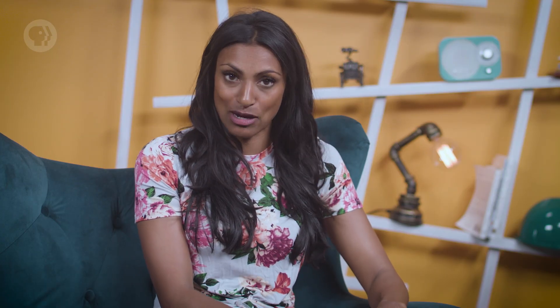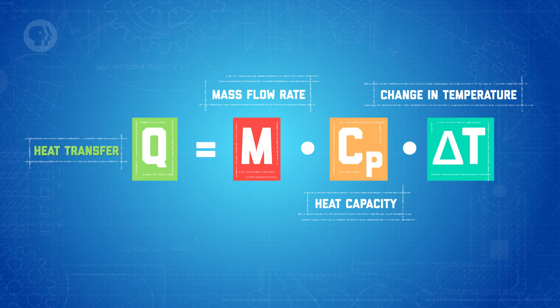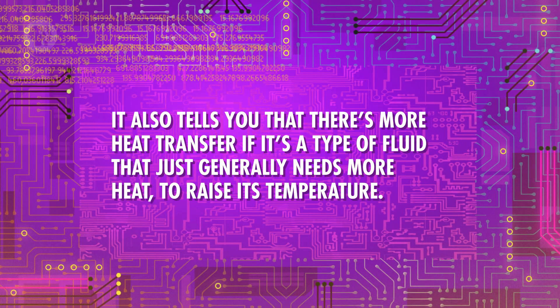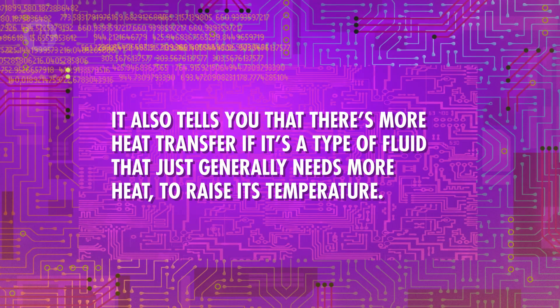There are two main equations for heat transfer that you can use to figure this out. The first looks at each fluid individually and defines heat transfer, represented by the letter Q, as the product of three of the chosen fluid's properties: its mass flow rate M, or how fast it's moving; its heat capacity C, or how much heat you need to raise the fluid's temperature; and its change in temperature, delta T, after it passes through the heat exchanger. This equation tells you that if there's a greater change in fluid's temperature, there was more heat transfer. It also tells you that there's more heat transfer if it's a type of fluid that generally needs more heat to raise its temperature. Finally, it says it takes more heat transfer to accomplish a given temperature change in a fluid that's moving really fast — if each particle of fluid isn't staying in the heat exchanger for very long, you need more heat transfer to raise its temperature quickly before it leaves.